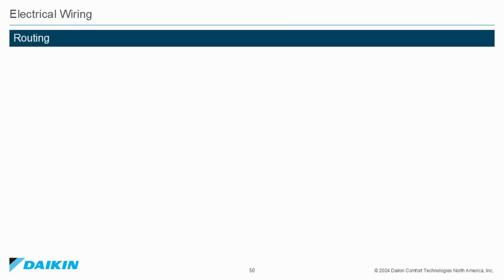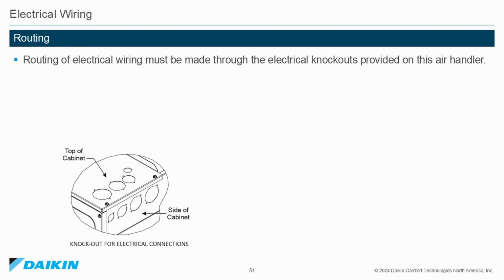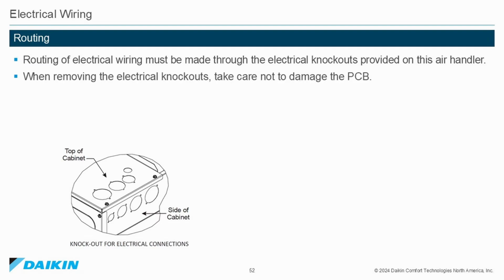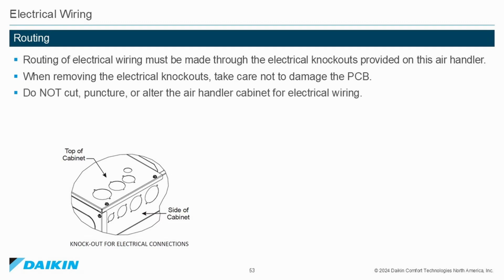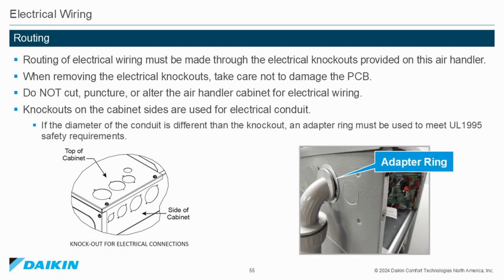Electrical wiring. Routing. Routing the electrical wiring must be made through the electrical knockouts provided on the Airhandler. When removing the electrical knockouts, be careful not to damage the circuit board. Do not cut, puncture, or alter the Airhandler cabinet for electrical wiring. Knockouts on the cabinet side are used for electrical conduit. If the diameter of the conduit is different than the knockout, an adapter ring must be used to meet UL 1995 safety requirements.